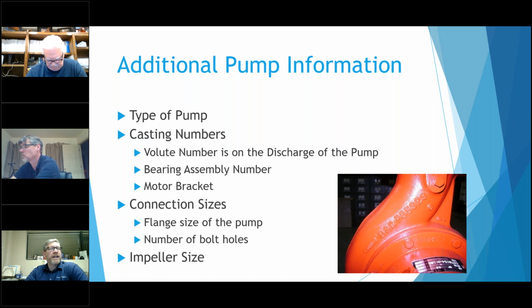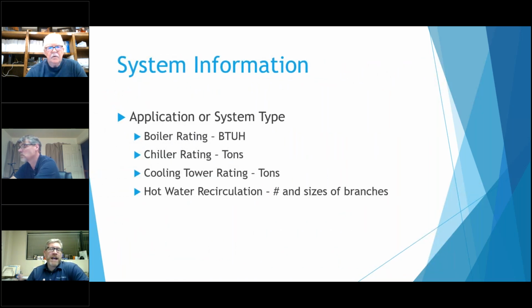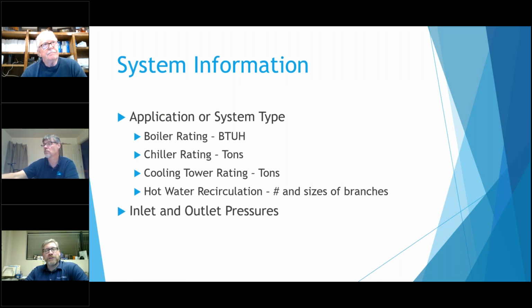We also ask for the impeller size. If all else fails, there have been a couple of times where we've gone back and re-engineered the system. We ask those questions to almost redesign the system by itself, to say, okay, this pump will work. Because some of those have no information whatsoever on them, we'll take some guesstimates and use the boiler rating or the chiller rating to come up with a flow, and of course, the length of the loops and so on to get a pressure reading.